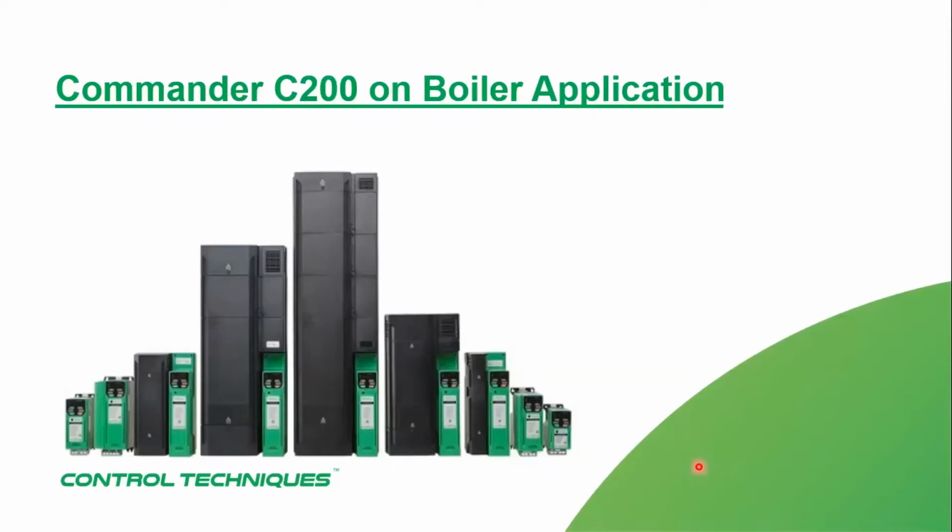We want to share about the Commander C200 on boiler application. For the maximum capacity that we have commissioned, in my experience in Indonesia, the biggest one is 21 ton, which uses a 132 kilowatt Commander C200. So it's still acceptable for the maximum capacity of the C200. If more than that, I suggest you use the F300 version of our VSD.